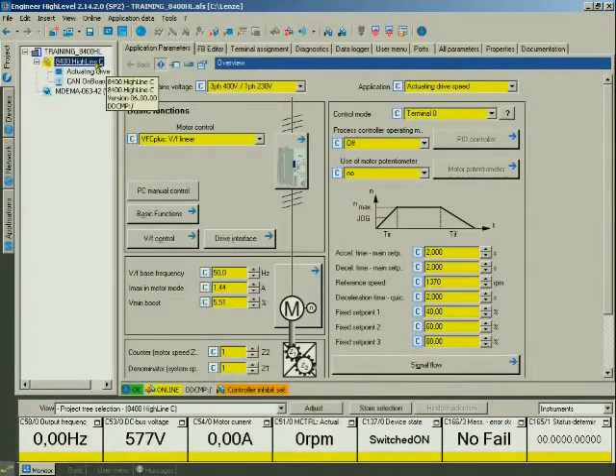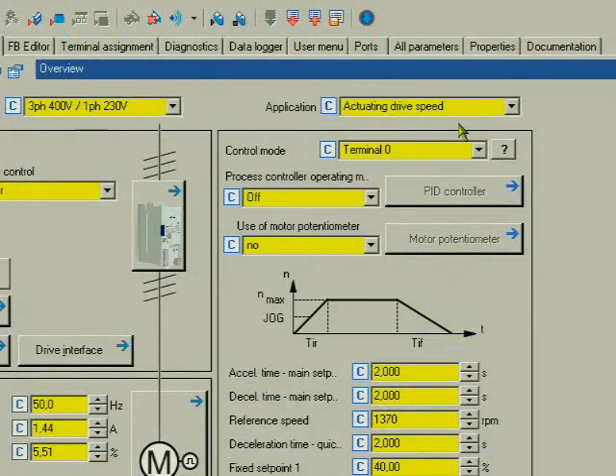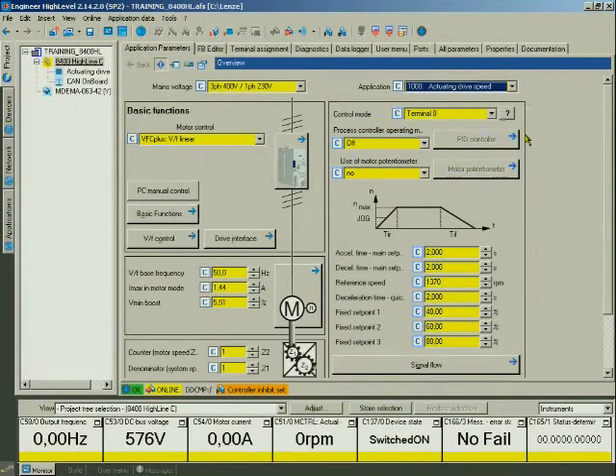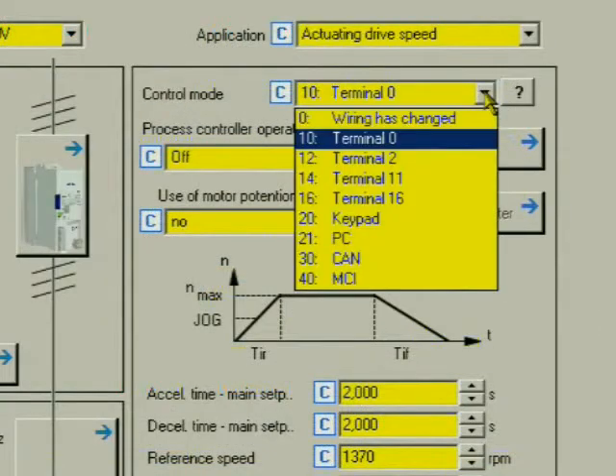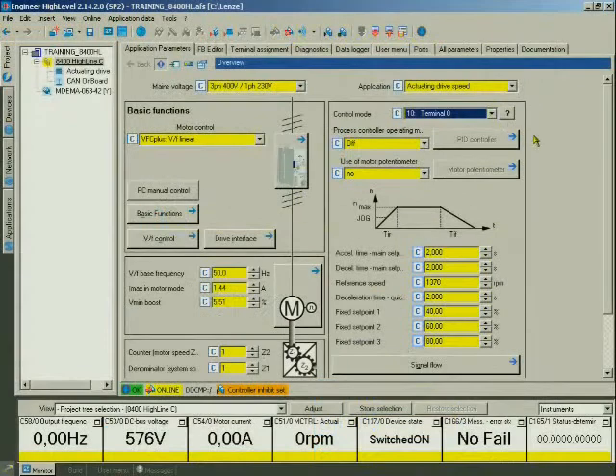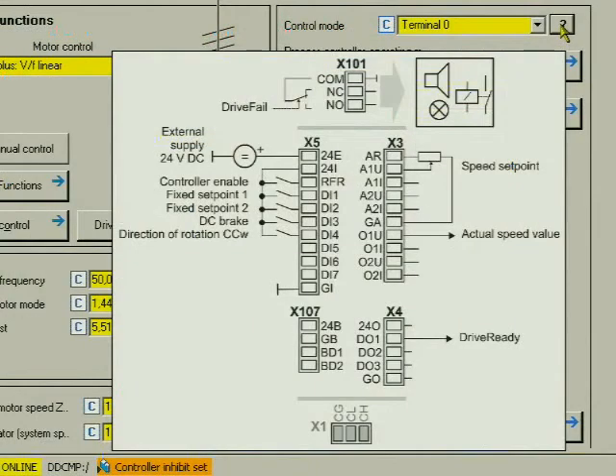The device overview will open. Check whether the Actuating Drive Speed application is selected. Our test setup is wired according to the Terminal Zero control mode, therefore we select this control mode. If you click the question mark, you can view the active terminal assignment.